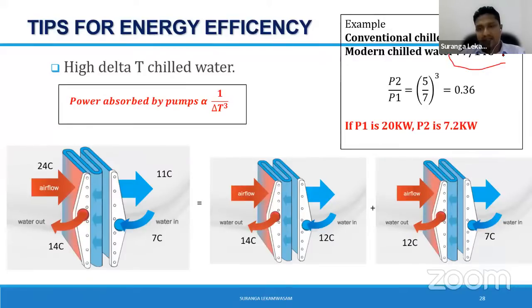But if you go for high delta T like 7/14, 6/15, whatever it is, you can understand with your fundamentals, your chill water pump power absorption is inversely proportional to the cube of delta T, right? So in a case study I have used, if you go for 7/12, 5 degrees, versus 7/14, 7 degrees, this is the scenario. For 7/12, if you use a 20 kilowatt chill water pump, for 7/14 you can use a 7.2 kilowatt chill water pump, more or less 3 times reduction in capacity. That's a huge amount, which you can get the benefit of if you go for this nature of work, right? So if anyone still doubts this high delta T, I have elaborated with a diagram so that you can understand.